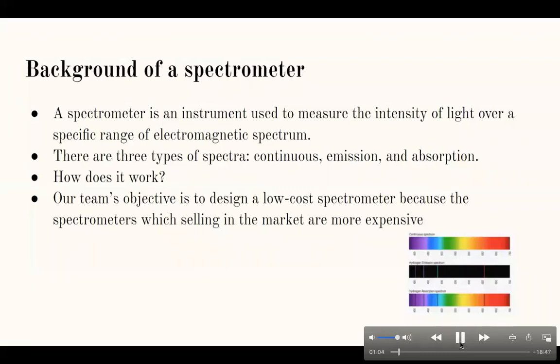So how does a spectrometer work? First of all, light passes through a slit, which may have a filter installed to control the width of the slit. Then the light transmits through a biconvex lens to make it more focused on the focal point, because the light waves are parallel and coherent. It goes to a diffraction grating, which splits photons by wavelength. The diffraction grating then directly spreads light on the camera detector. So the individual pixels of the detector are recognized by the transmitted light. Each pixel represents a portion of the spectrum which is translated into an answer with custom software. So our team's objective is to design a low-cost spectrometer, because the spectrometers selling in the market are more expensive.